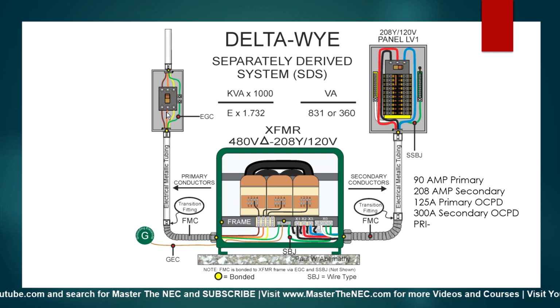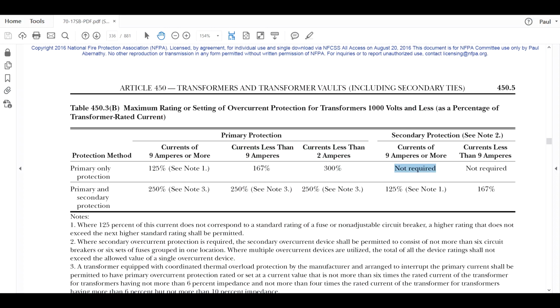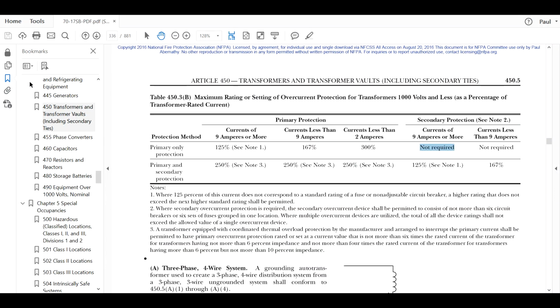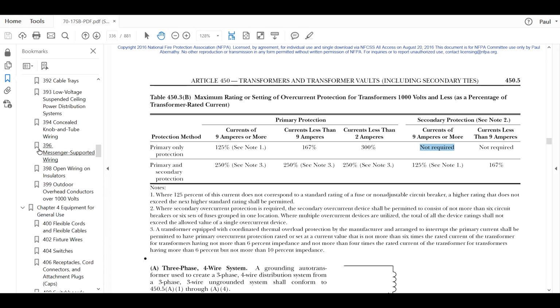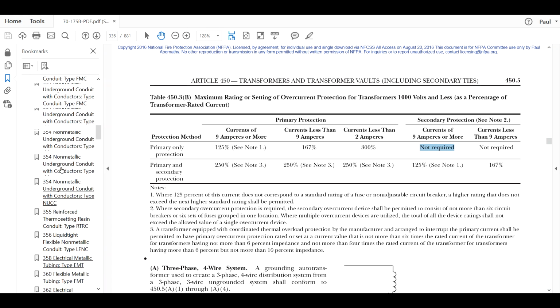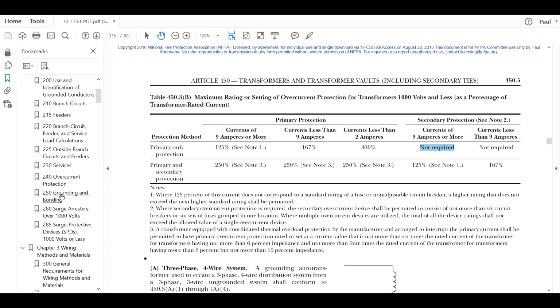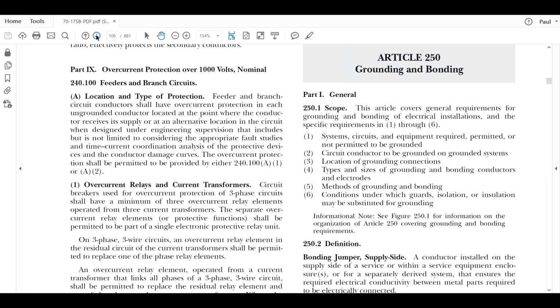Well, we know this is a 125. We know that we use 250.122 to size equipment grounding conductors that are on the load side of the overcurrent protective device. So based on that, we're going to go to the National Electrical Code, and we're going to go to 250.122. Size that little sucker.